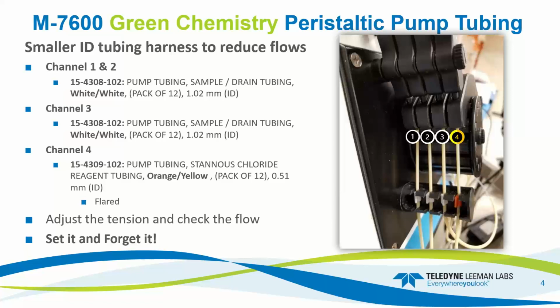So in channels 1 and 2, which are the drain lines, and channel 3, which is the sample uptake, we use a white tubing, which is part number 15-4308-102. So the first three channels are all identical. And then in channel 4, we use the orange-yellow tubing, which is part number 15-4309-102. And we kept the T connections the same just to keep everything simple. The only thing we changed were the tubing themselves.